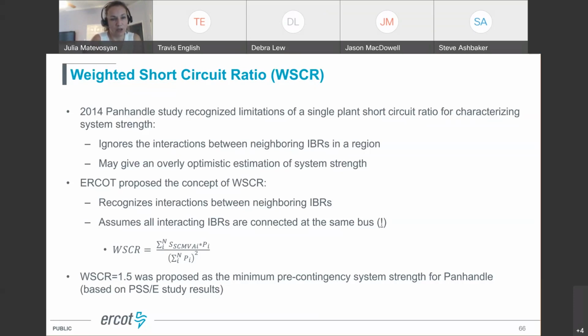And so with that, ERCOT proposed the so-called weighted short circuit ratio that recognizes interactions with other inverter-based resources. But the assumption is that all inverter-based resources are connected to the same bus. And so you calculate weighted short circuit ratio as the sum of short circuit power at each node in this area times power of inverter-based resources in this area, divided by the sum of power of inverter-based resources in this area, squared. So it's weighted by the power of each inverter-based resource. And a weighted short circuit ratio of 1.5 was proposed as a minimum pre-contingency system strength in the Panhandle area based on results of PSS/E study.